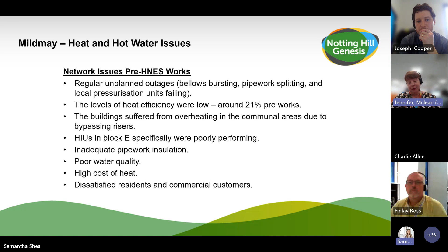Before HNES funding, we had identified that within the main plant room there were too many heat pumps, leading to inefficiencies in terms of energy consumption. We had approximately 8 in the main plant room, as well as the pumps within the substations. We were able to identify that we could at least halve the number of pumps and therefore dramatically reduce the electricity consumption from that site.